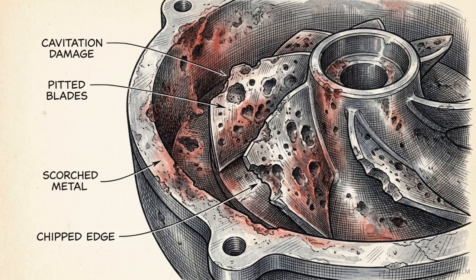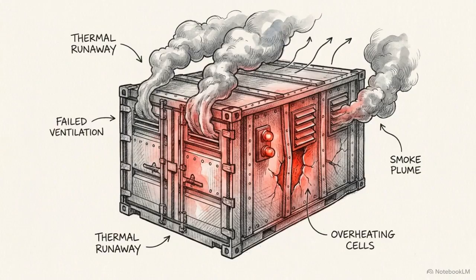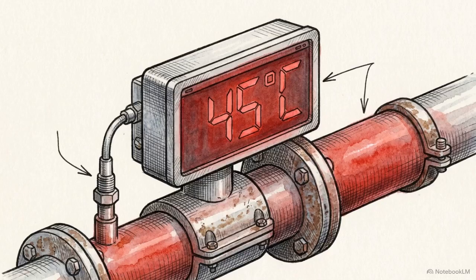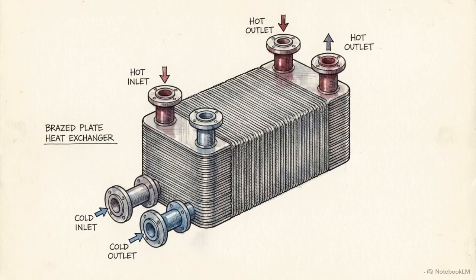Failing to pinpoint this intersection during the design phase ensures the pump will either run dry and cavitate or fail to overcome the pressure drop, leading to uneven cooling and eventual thermal failure. Once the primary coolant completes its circuit through the batteries, it is saturated with heat. It must be chilled before it cycles back. The primary loop carries this hot coolant into a brazed plate heat exchanger.